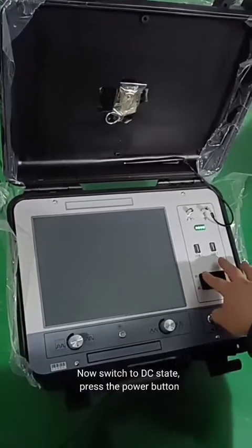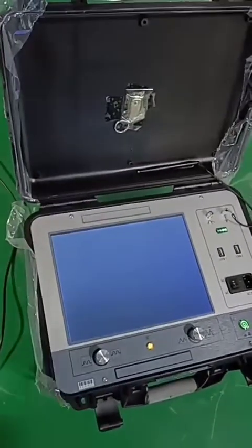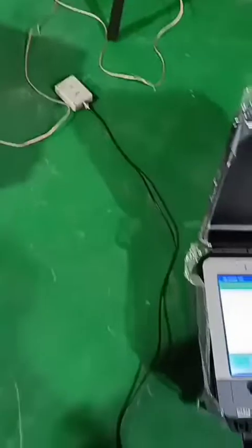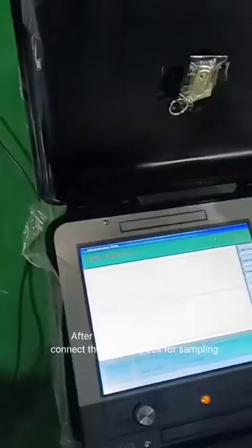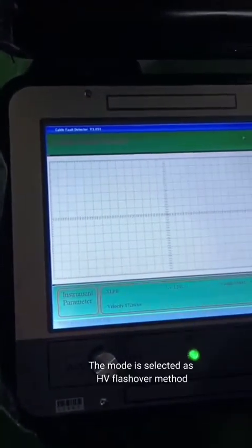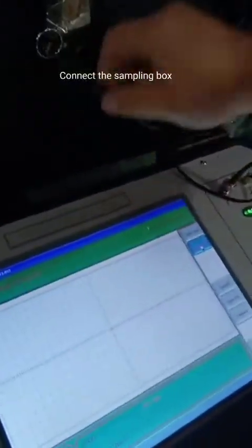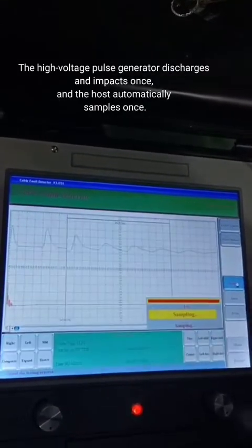Now switch to DC state. Press the power button. After the fault clicks through, connect the sampling box for sampling. With speed 170 meters per microsecond, the mode is selected as HV flashover method. Connect the sampling box and click to sample.